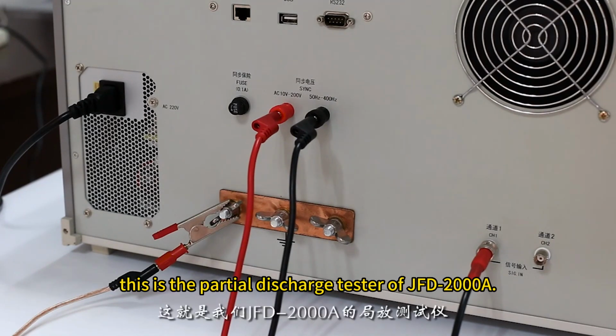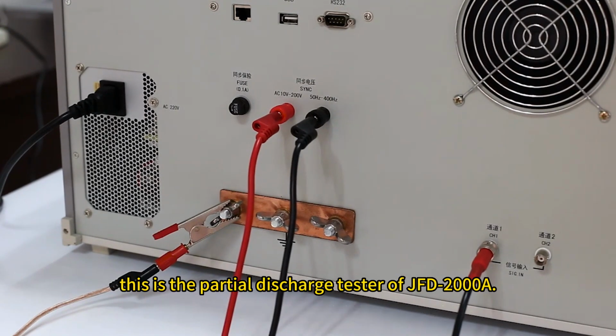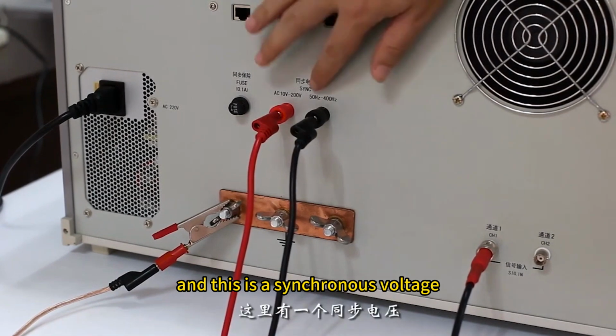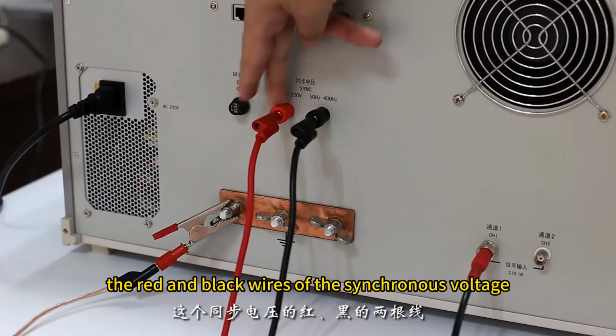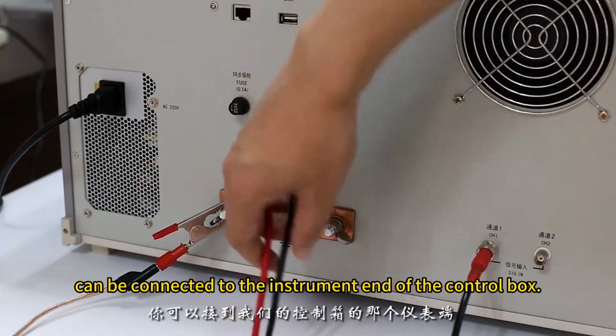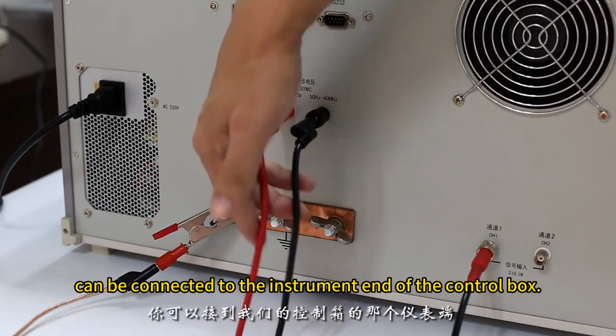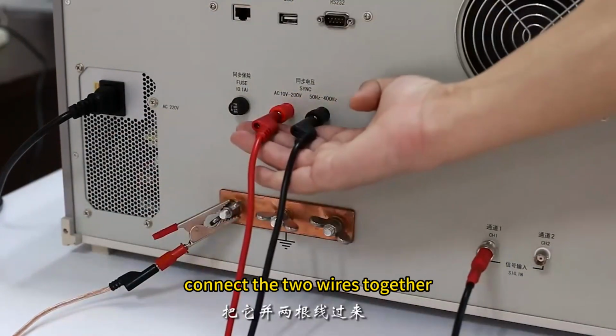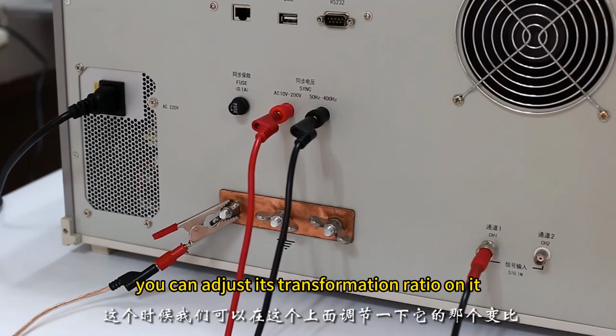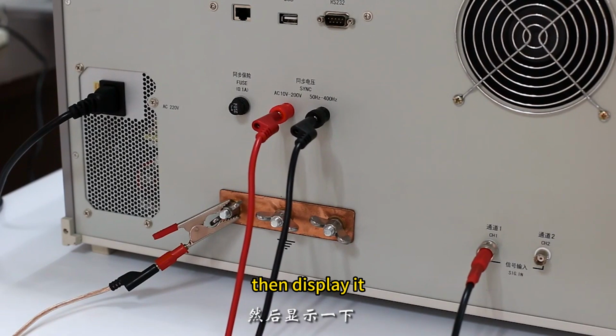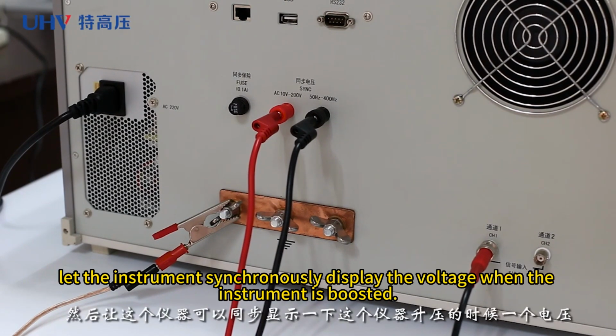This is the partial discharge tester JFD 2000A. And this is a synchronous voltage. The red and black wires of this synchronous voltage can be connected to the instrument end of the control box. Connect the two wires together. At this time, you can adjust its transformation ratio on it. Then display it. Let the instrument synchronously display the voltage when the instrument is boosted.